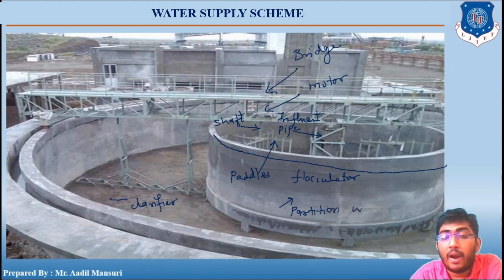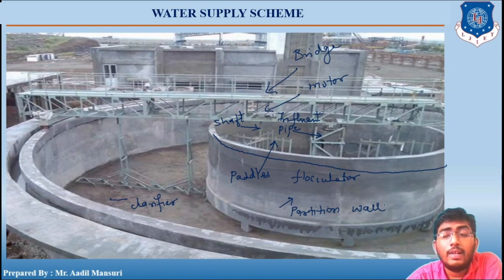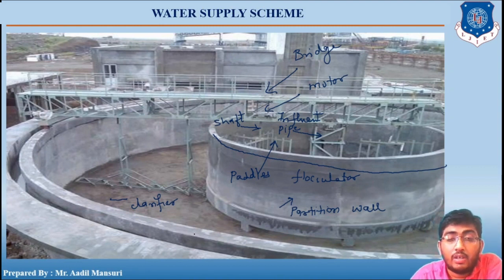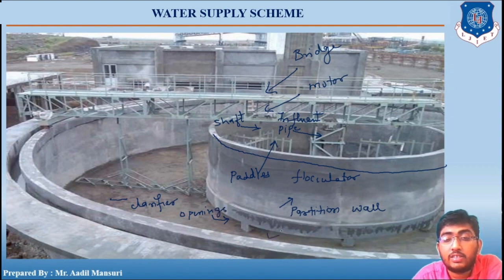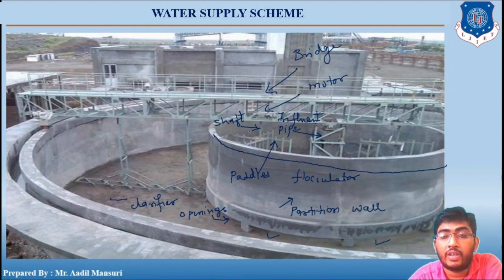This is the partition wall. The water will enter the clarifier from below the partition wall. These are the openings you can see - there will be openings all around the flocculator, below the partition wall.